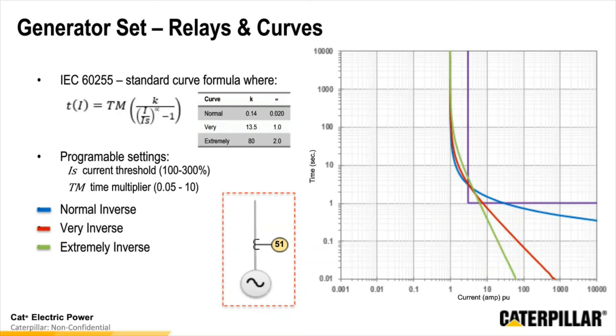So there's not only one curve available to you. There typically is the normal inverse curve, which we see as the blue curve on the graph. We also have the very inverse curve, which would be the red curve, that starts giving us slightly more current to the left side and slightly less on the short time range. Or the extremely inverse, which provides even more current available, or more time available, to the left side of the curve, and it provides us less current capability on the short time range of the curve.